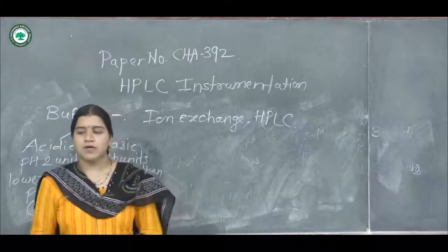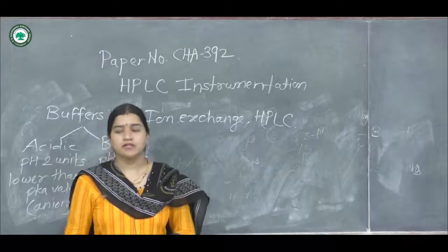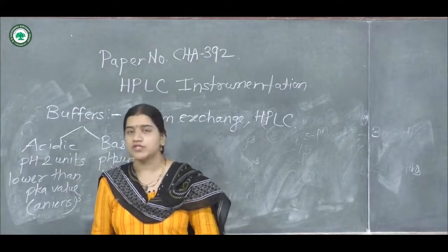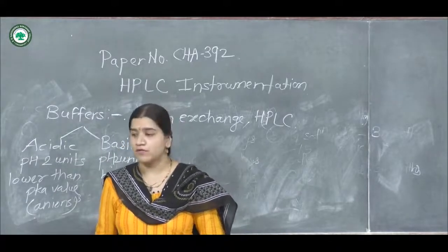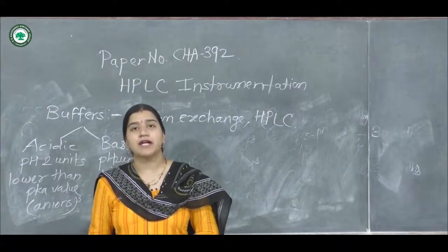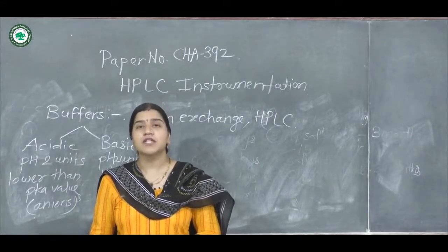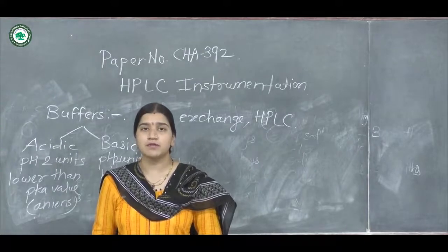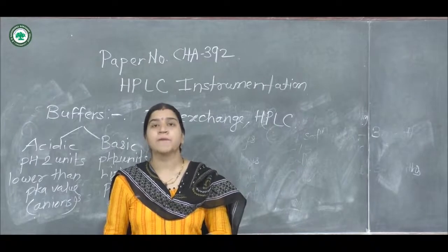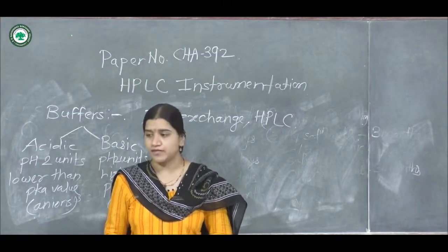Whenever you are using a buffer solution in HPLC, you have to first filter the buffer, and after the process of filtration, then you can use the buffer for the further process, because there are chances of bacterial growth or fungal growth in a buffer solution. Hence it is very necessary to preserve the buffer in a clean bottle as well as to use a buffer solution of high purity, and you have to first filter it and then use it in HPLC analysis.